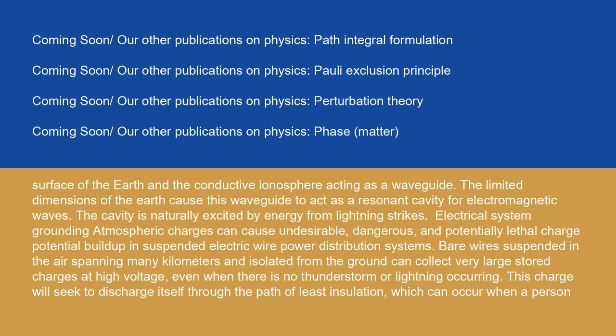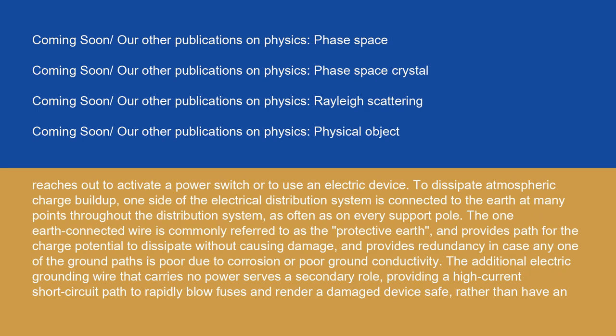Electrical system grounding: atmosphere charges can cause undesirable, dangerous, and potentially lethal charge potential buildup in suspended electric wire power distribution systems. Bare wires suspended in the air, spanning many kilometers and isolated from the ground, can collect very large stored charges at high voltage, even when there is no thunderstorm or lightning occurring. This charge will seek to discharge itself through the path of least insulation, which can occur when a person reaches out to activate a power switch or to use an electric device. To dissipate atmospheric charge buildup, one side of the electrical distribution system is connected to the Earth at many points throughout the distribution system, as often as on every support pole. The one Earth-connected wire is commonly referred to as the protective Earth, and provides a path for the charge potential to dissipate without causing damage, and provides redundancy in case any one of the ground paths is poor due to corrosion or poor ground conductivity.